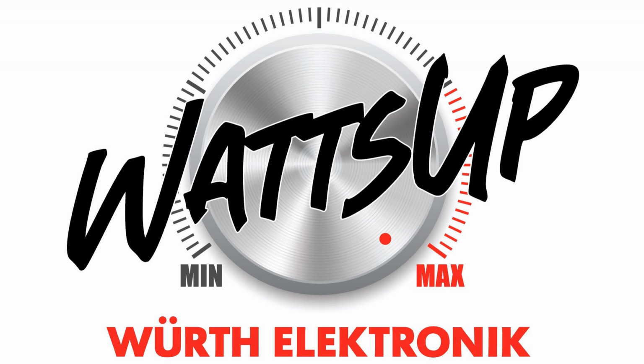So according to different international standards, there are different definitions which we can find in those standards. For example, the already mentioned 5 milliamps for 2-second application of the voltage, or 3 milliamps for a longer period, for example, 5 seconds. Yes, and this maximum current must not be exceeded.